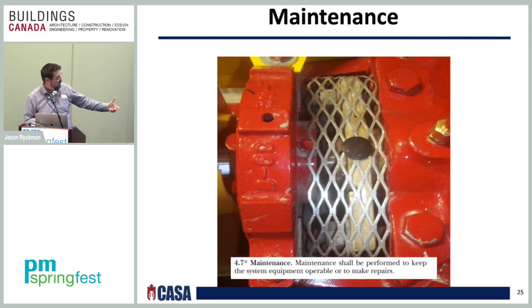Maintenance, again, shall be performed to keep the system equipment operable or to make repairs. This is an example of a drip tray for a fire pump. If you look at a fire pump and you don't see little drips going into that tray in front of the pump, I guarantee you probably have a fire pump issue, because the glands within the fire pump have probably seized, and you're probably not going to start your fire pump system. So you have to see one drip, usually one drip per second. It could be quicker. As long as there's some sort of water going into that water tray for the fire pump, that's the main thing. And that's part of a maintenance type of procedure.